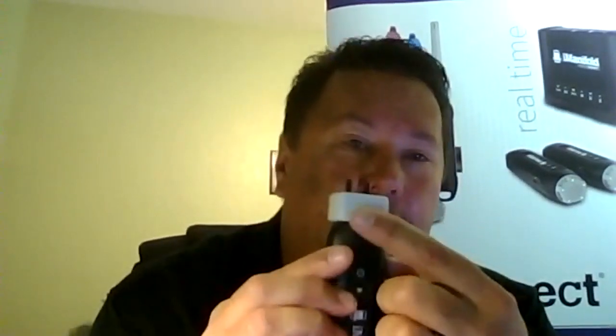Yep, we do. When you're using the 921M, it pairs into the system just like anything else. Now, just remember when you take a look at it on the tip here where you've got your plugs, there's magnets on the back so you can stick it onto a piece of ductwork. It's very faint and hard to see, but you've got minus and plus over here. Glad to see eyesight going, right? So when you plug in your hoses here, you've got minus and plus to go to either the supply or return side.